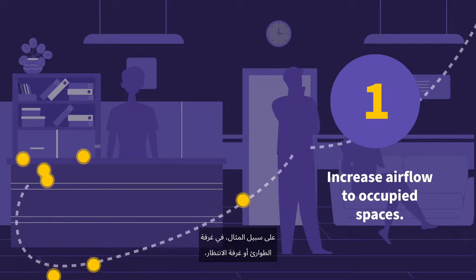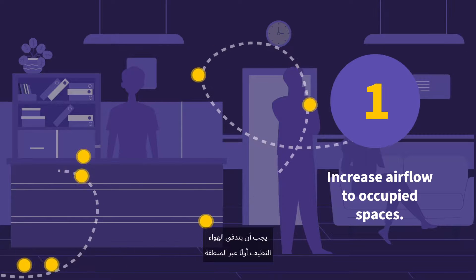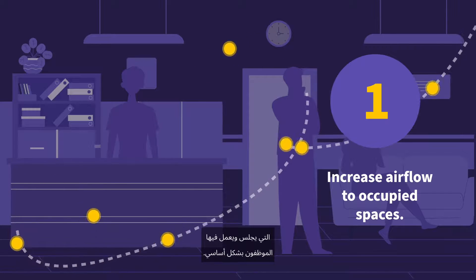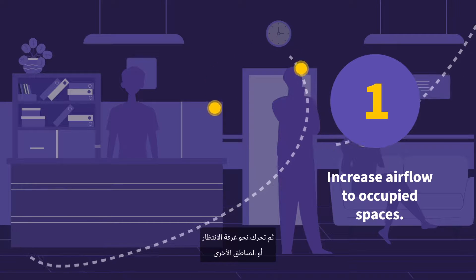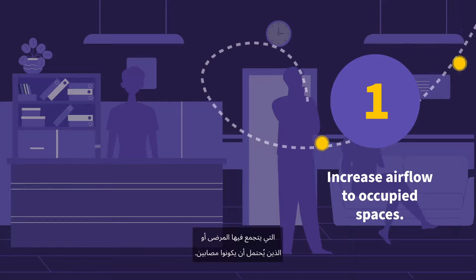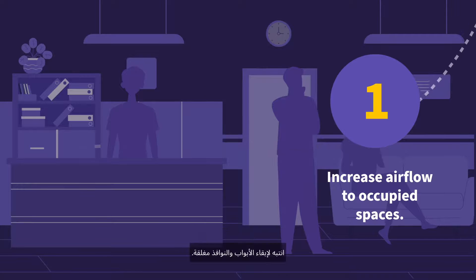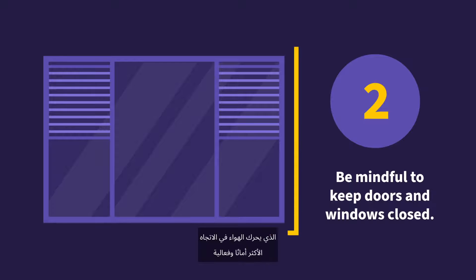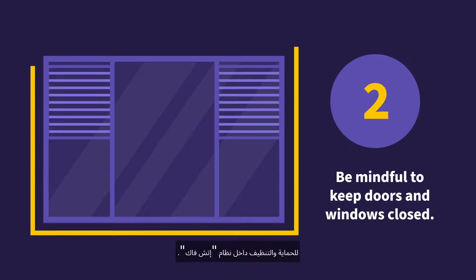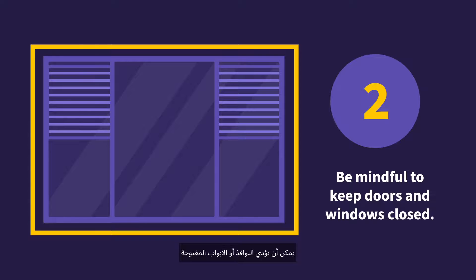Increase airflow to occupied spaces when possible and direct clean airflow to contaminated zones. For example, in an ER or waiting room, clean air should first flow through the area where employees primarily sit and work, then move toward the waiting room or other areas where sick or potentially infected patients gather. Be mindful to keep doors and windows closed. Medical buildings are designed to allow for pressurization that moves air in the safest, most effective direction for protection and cleaning within an HVAC system. Open windows or doors can throw the entire system off balance and make it ineffective.